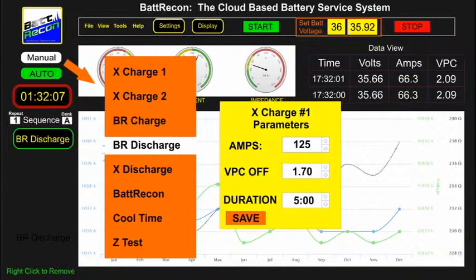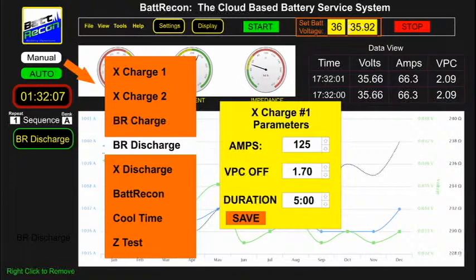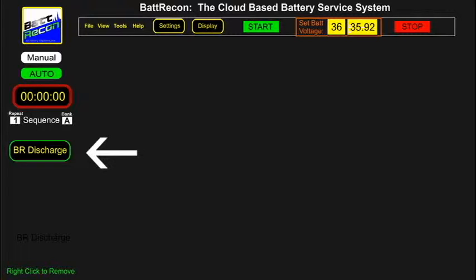Type the number 125 in the amps block, or use the cursor to move the values up or down. Type 1.70 in the VPC off block — this is the average cell voltage at which the command and control center will stop the discharge test. Click on save. This closes the window and adds the BR discharge tab in the left-hand operators panel area.